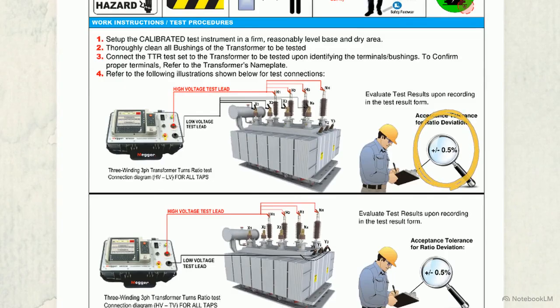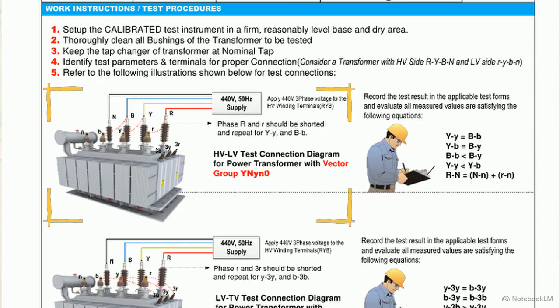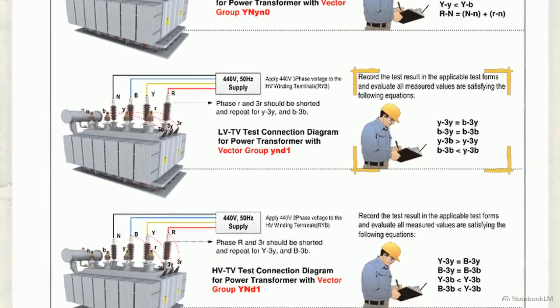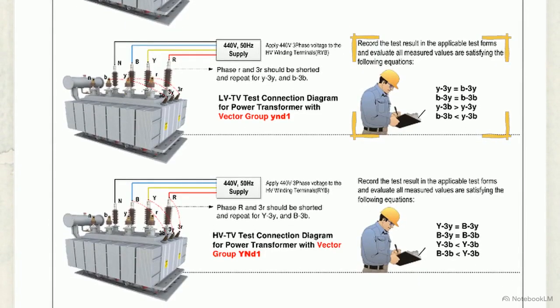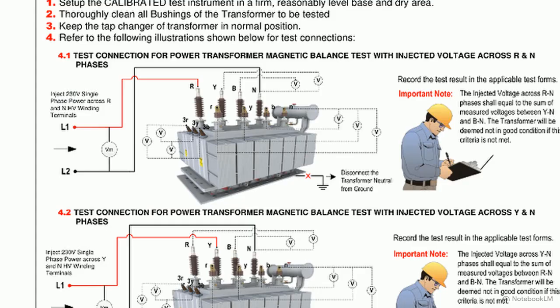These schematics demonstrate vector group testing. By applying specific phase shorting connections and solving the corresponding voltage equality equations, we confirm the physical terminal identification and the correct phase displacement clock number. This reference details magnetic balance testing. When we inject a low-voltage AC signal into one phase, it induces predictable voltages on the remaining two.